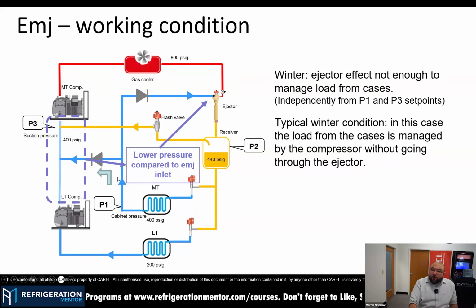The preferred path for the refrigerant will be going here, right? And not going in the ejector direction. And at this point, this check valve has more effect because I would avoid the flow back from the ejector. Remember that I have the needle controlling the flow from the gas cooler, but here from the liquid receiver and this port, we are pretty much at the same pressures if I don't have the ejector effect. So I would have higher pressure, and this check valve would avoid flow back.